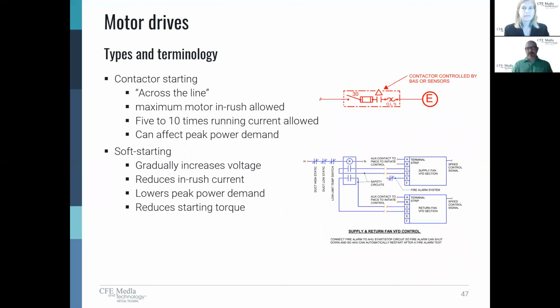Now, if I want to start a motor, I talked before about digital on-off controls with building automation systems. I can do what's called a contactor or an across-the-line start. That's where I simply say go, and I give a pump or I give a motor all the energy all at once. Well, we're going to have a lot of inrush associated with that, which can be problematic. Now, there's a variety of ways that I can generally start that motor. I can use a couple different what we call soft starters to maybe ramp up the voltage or kind of push the motor very gently and get it going. Now, which one you're going to use is really going to depend on the electrical parameters and what that electrical system can handle.